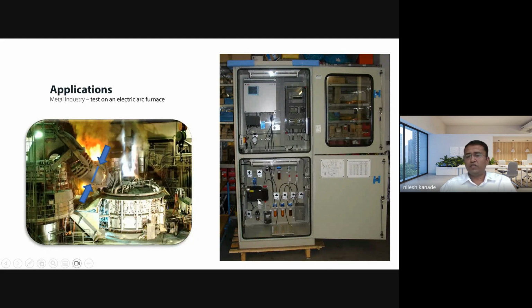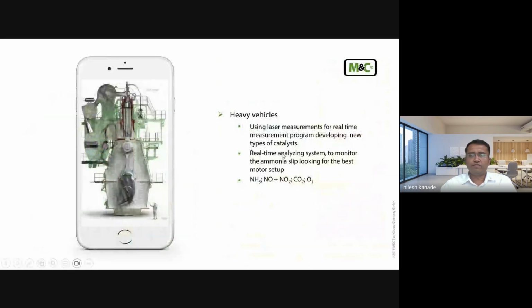There are a number of equipment required, such as a gas cooler, a gas dryer, gas pumps and gas filters. Some moisture detectors, pressure sensors, flow sensors and temperature sensors need to be installed in that panel. When the sample gets conditioned with very low pressure, very low temperature and very little moisture content, it is fed to your analyzer. This is the complete set of the sampling system with analyzer.